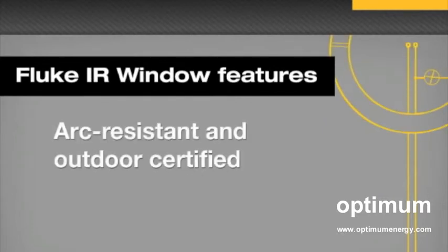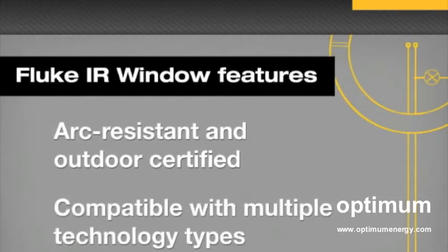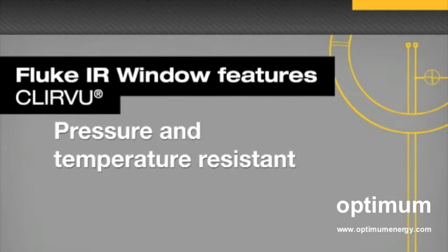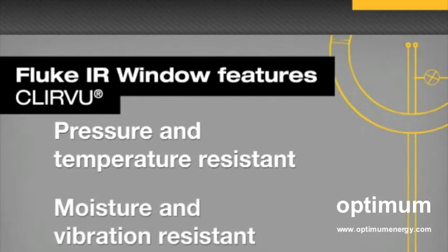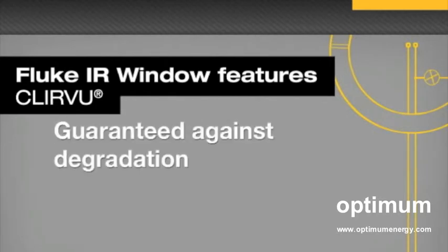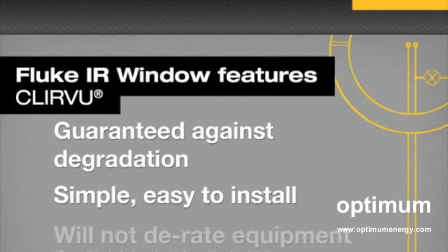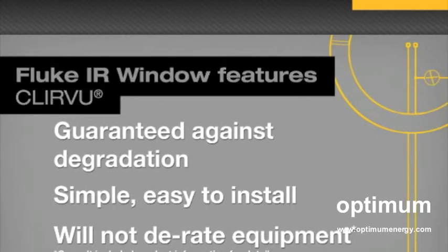The Fluke IR Window includes the following features: arc-resistant and outdoor-certified; compatible with thermal, ultraviolet, visual, and fusion technologies; made with CLIRVU crystal designed to withstand the severe pressures and high temperatures of arc-fault events; moisture and vibration-resistant; guaranteed never to degrade even when subjected to mild acids or alkalis. The simple, easy-to-use installation process should not compromise or derate equivalent UL-rated enclosure integrity if installed according to proper procedures and guidelines, and you can do it in about 10 minutes.